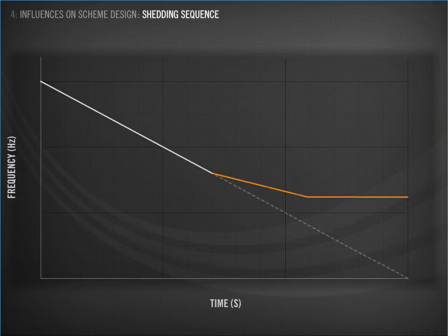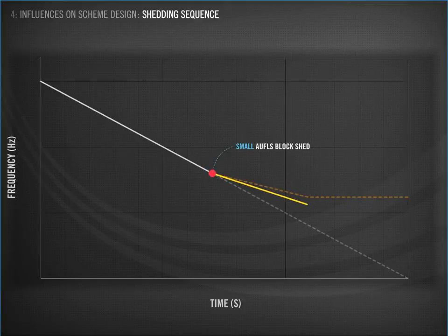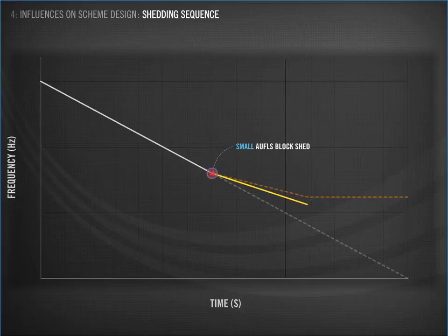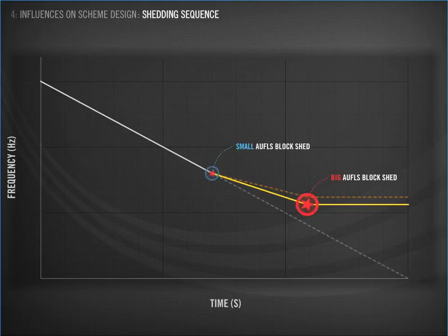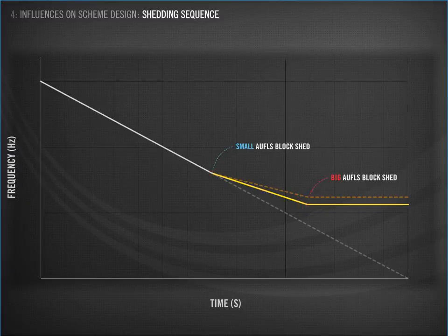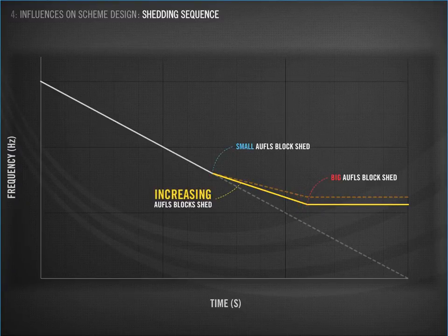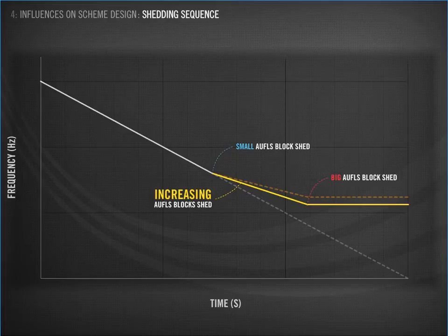In this second example, we start with a smaller AUFLS block. In other words, we lightly apply the brakes, and the frequency continues to fall at a faster rate than in our previous example. The frequency falls further before the second bigger block triggers. The frequency decline is arrested and the line levels out. We call this design an increasing scheme.